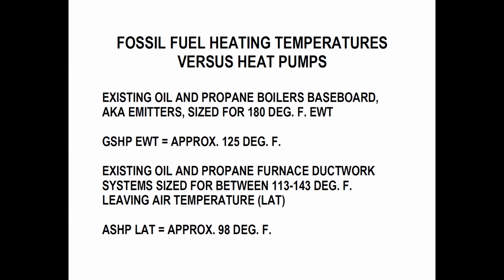When I put my geothermal in, I had to take my old baseboard out and put in these very big European style baseboards because they have more surface area that delivers as many BTUs as I need for the space with lower temperature water. Same thing goes for forced hot air systems, oil or propane. The leaving temperatures for them are in the 113 to 143 range, versus an air source heat pump, which is going to get you 98 degree-ish temperature going into the space.